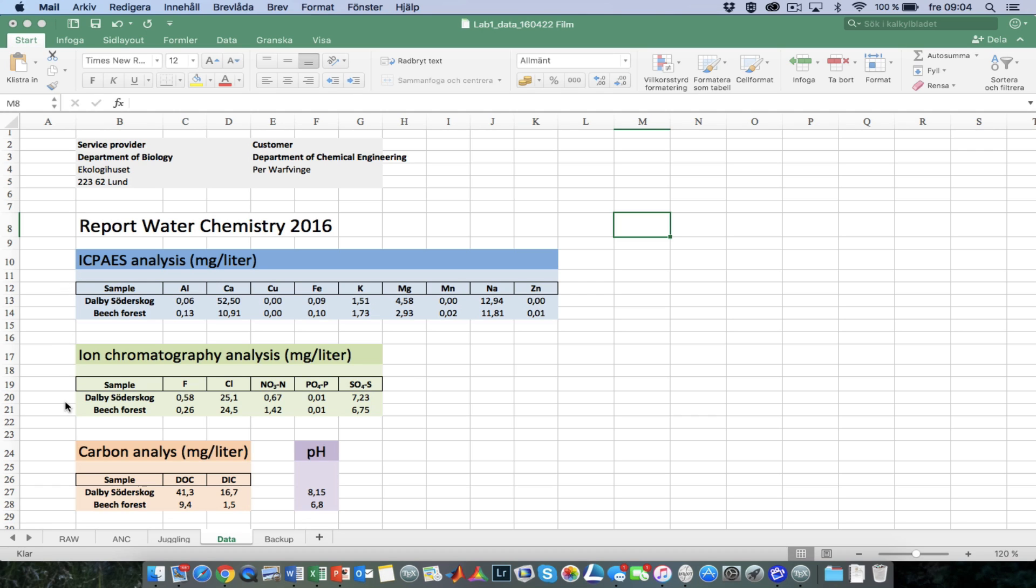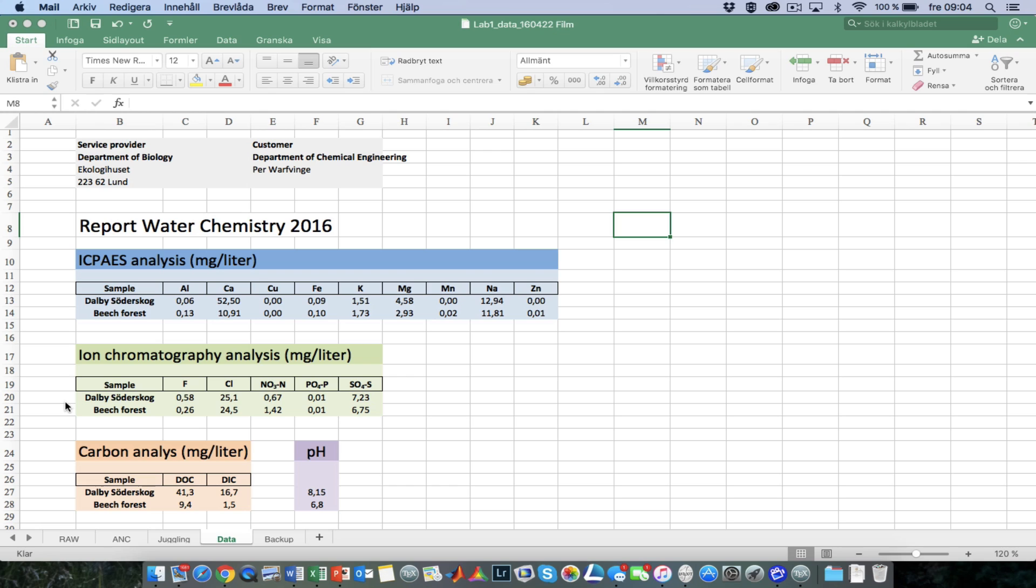Since each element emits light with a specific characteristic wavelength, you can separate the elements and you can determine the concentrations through the intensity of light that they emit. The piece of data in green comes from an ion chromatography analysis. It's a column, and you force the water sample through this column. Since the various anions in the water sample get absorbed and released at different rates, they will be separated as they pass through the column, and at the end of the column there is a detector that determines how much of various substances come through.